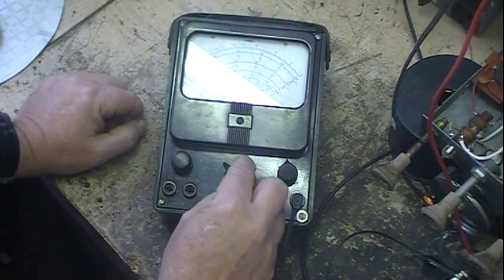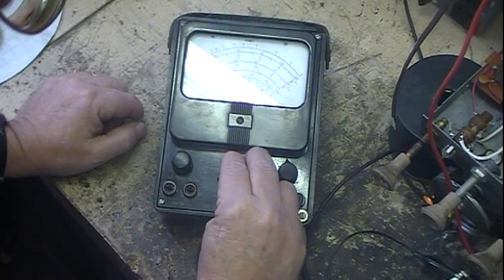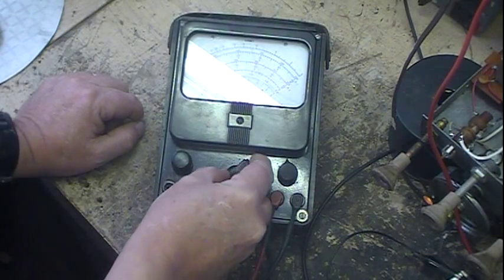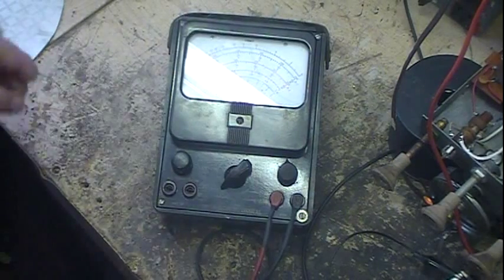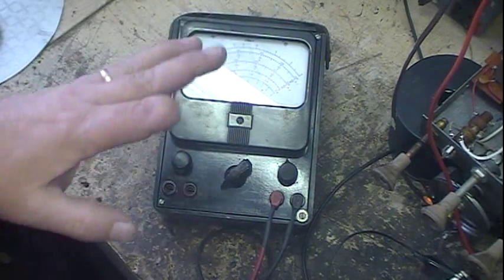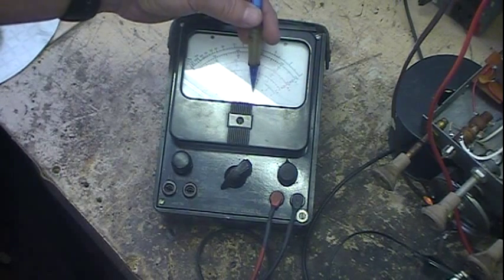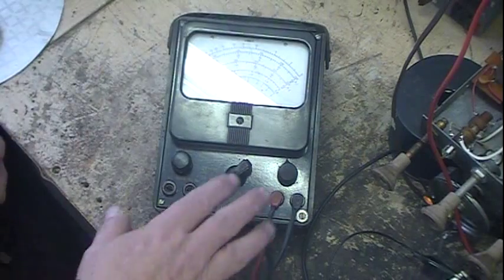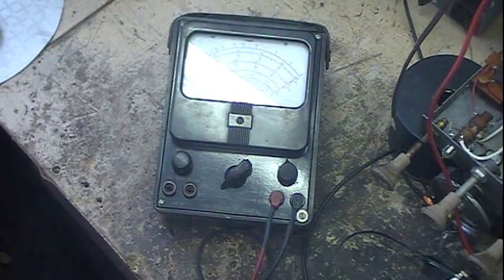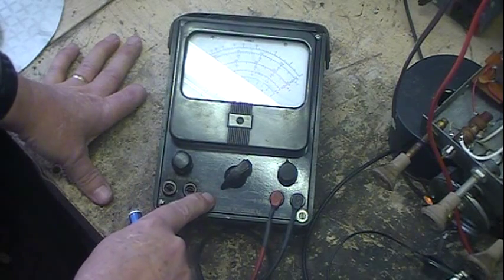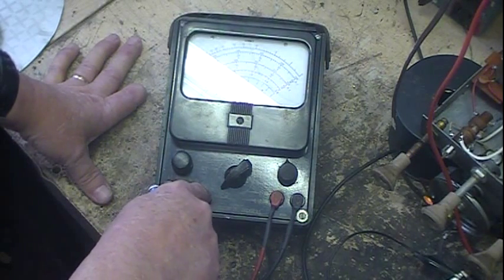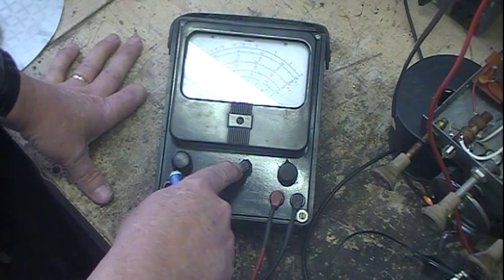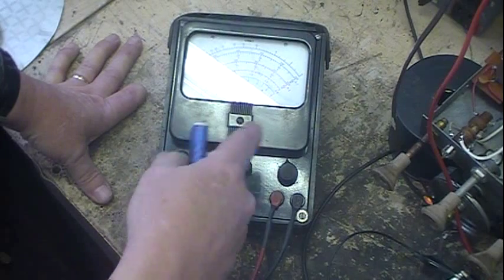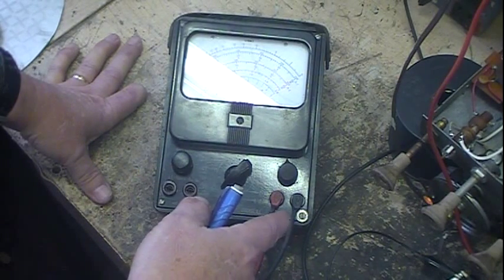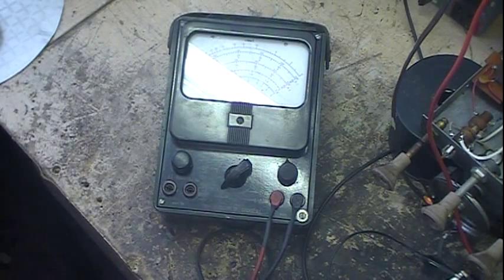Okay, now I'm going to turn this up. There's 10 volts, there's 50 volts. Let's go to 250. One thing to notice on this meter, it's not 10 megs. It's the VOM, 1,000 ohms per volt on AC, and I'm on AC because that's what I'm checking. So whatever scale I'm set on, I take 1,000 ohms times that. On the 250 volt scale, 1,000 ohms is just 250 times 1,000. So that's going to be quite high, about 2.5 megs.